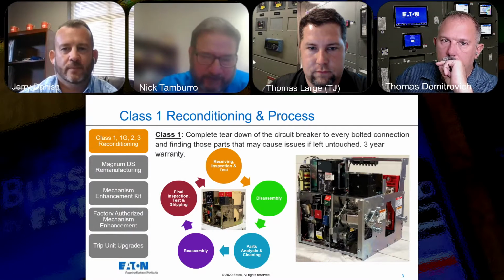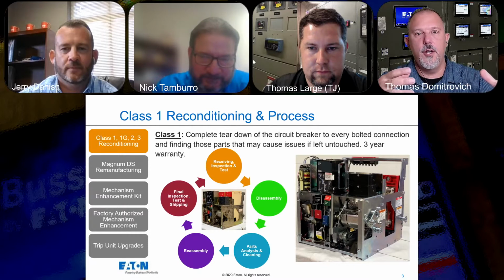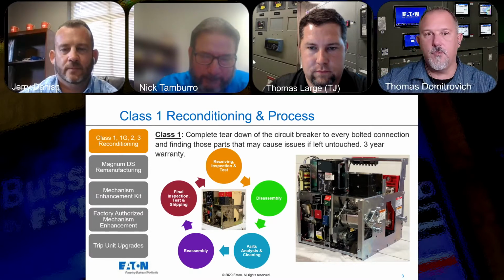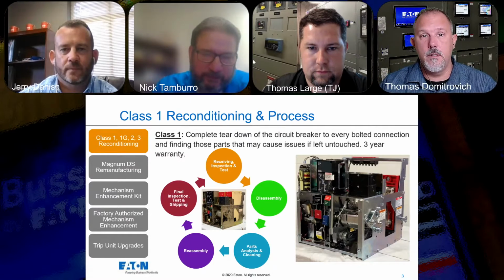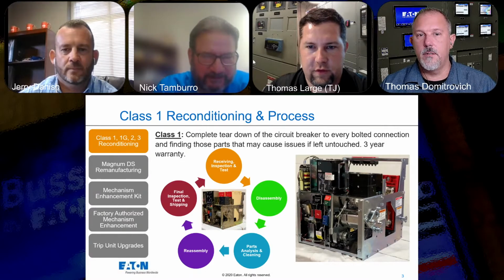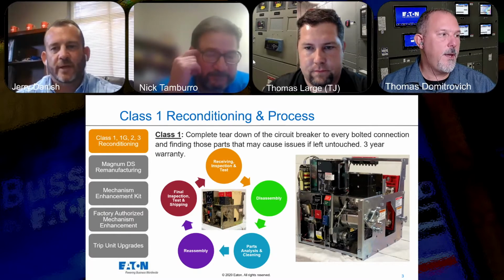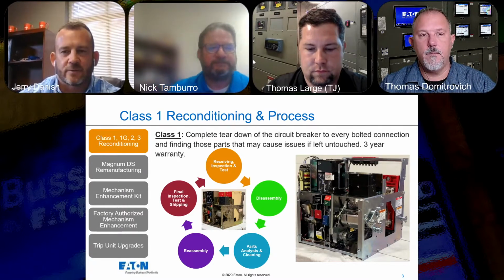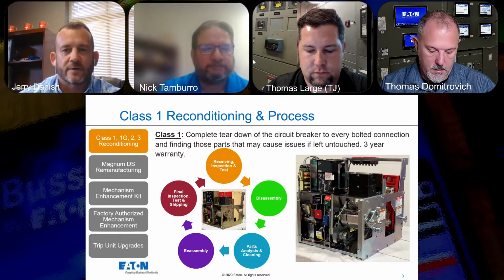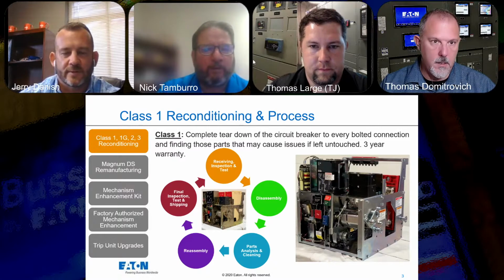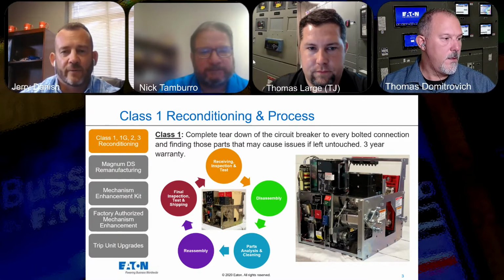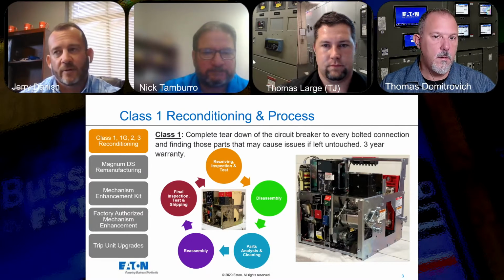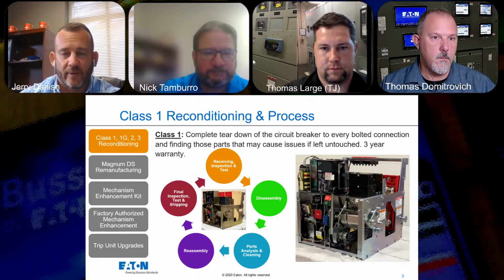But standard breakers, yeah. The reason the communications presents a challenge is the wiring from the communication module on the trip unit into the gear. They have two. The 10 series trip units use Incom, and Magnums use, I can't think of it. Is that RS-485 Modbus? Yes, Modbus. Okay. Tom, we talked a little bit about direct replacement breakers: you can take a direct replacement breaker, stick it in there, and if you had a problem and needed to take that breaker out, you can stick the old breaker back in. However, if you need to do any of that communications, or if you're converting that breaker from manually operated to electrically operated, then there are challenges behind why you couldn't stick the old breaker back in.